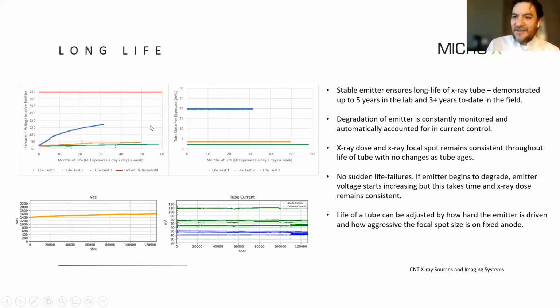But even if it did, and even if the emitter degrades, the dose and the focal spot remain consistent throughout that entire process. So when we do our life testing, we've actually looked at the dose and the focal spot consistently through the testing, and it doesn't change. And the reason it doesn't change is because you get the same current out of the emitter. The emitter itself, because of that redundancy, is using different carbon nanotubes at different times. So the voltage to drive it is increasing slightly. There's some point at which you run out of the voltage to drive it that you have in the system, and that's when it's considered at the end of life. But that is far beyond the typical use, and even in the most aggressive use, unlikely to happen. And that's validated both in the lab and in the field.